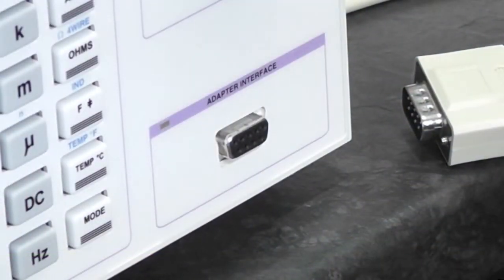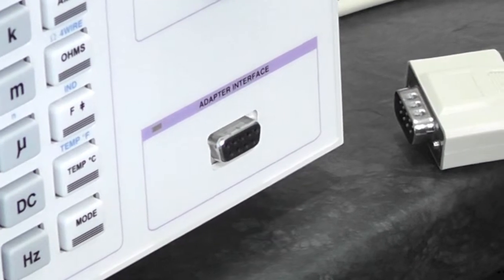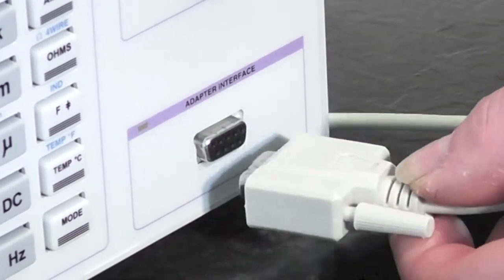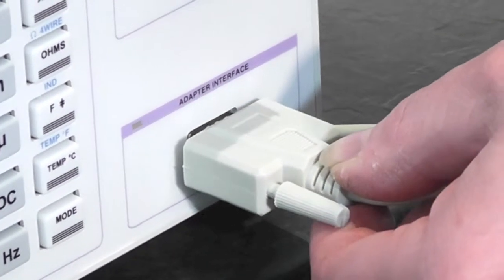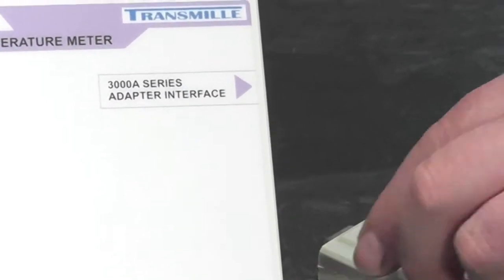To connect the adapter using the supplied lead, simply connect one end to the adapter interface on the calibrator and the other end to the adapter input.